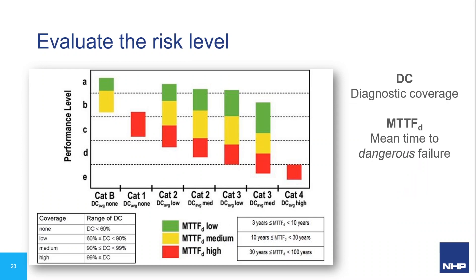Performance level is based on probability of dangerous failure per hour, but we still need to know what our safety control system should look like before doing calculations. There is a simplified process in the standards using a chart that looks at three factors: categories, DC (diagnostic coverage — the percentage of dangerous faults detected by the safety control system), and MTTFD (mean time to dangerous failure, given in years).